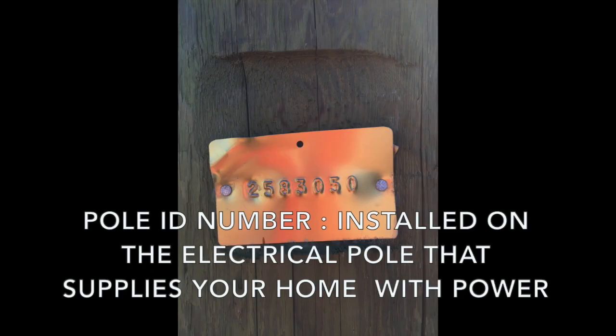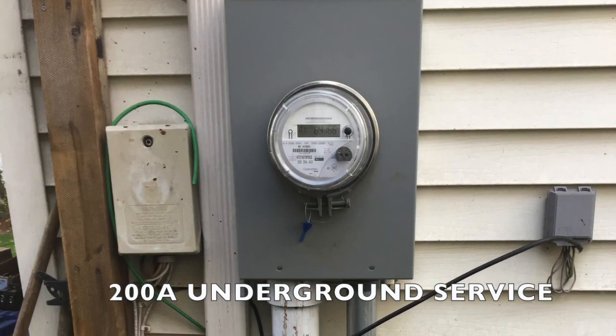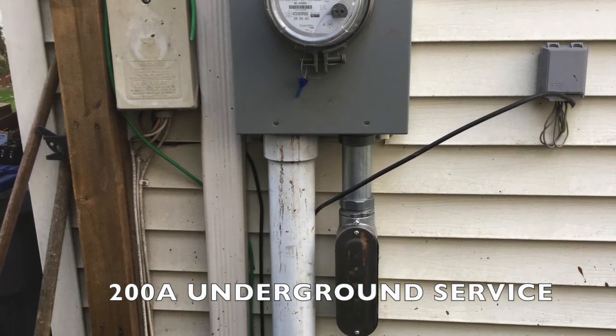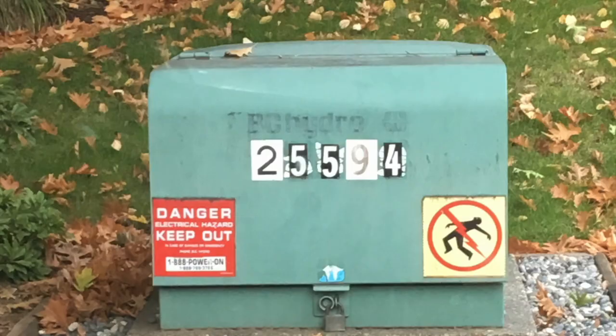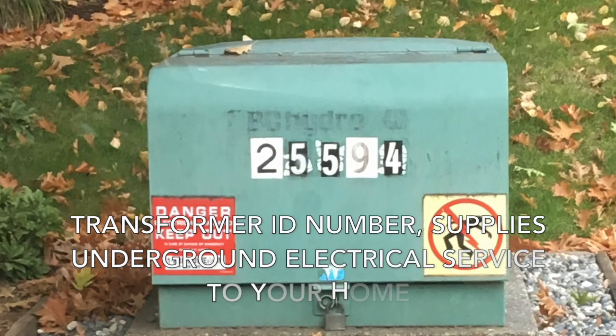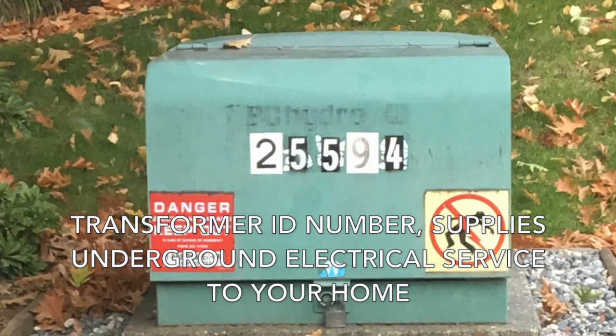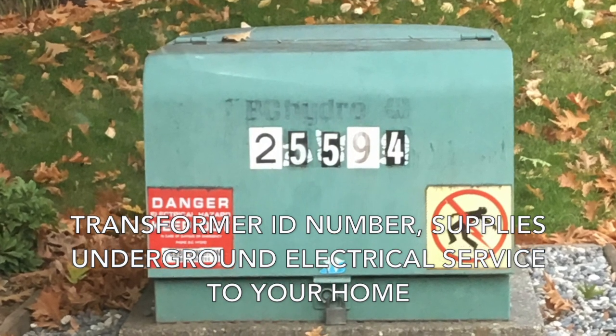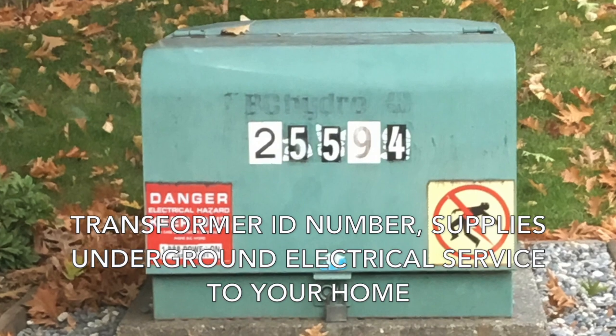In regards to an overhead service, this is the pole number that BC Hydro requires in order to schedule a date in which they will come and disconnect the old power and reconnect our new 200 amp service. So this is associated with an overhead service. Another common electrical service associated with homes is an underground electrical service. Associated with your underground service that supplies your home is a BC Hydro transformer ID number. This is the number that BC Hydro will require in order to schedule your service upgrade.